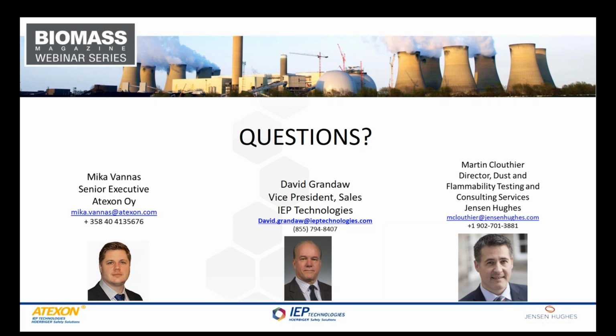No, and Bruce, no, actually, it will not. The flap will only work in one direction. I've not seen any flap-style valves that are bidirectional. There are other types of flow-activated isolation valves that can be used in some applications that are bidirectional. However, those have some very low dust loading limitations. I'm trying to remember off the top of my head, I believe 50 grams per cubic meter of airflow is the maximum for those styles. When we have an application in which we're trying to stop a deflagration from traveling from either vessel, then generally we would either use a chemical barrier or a high-speed isolation valve.